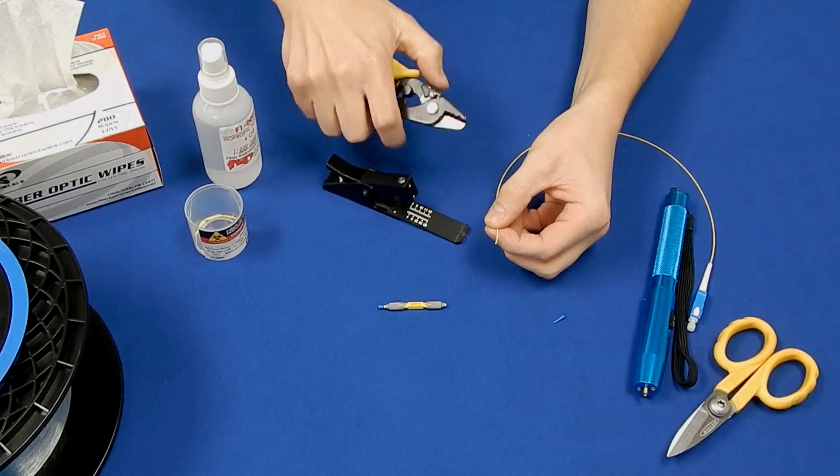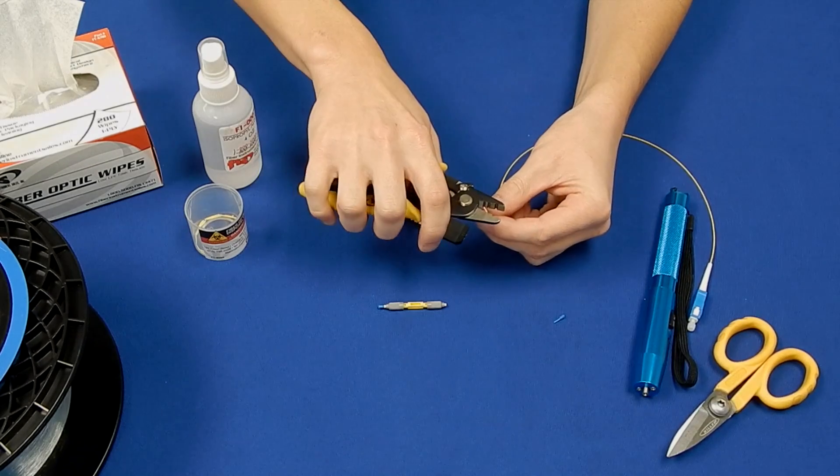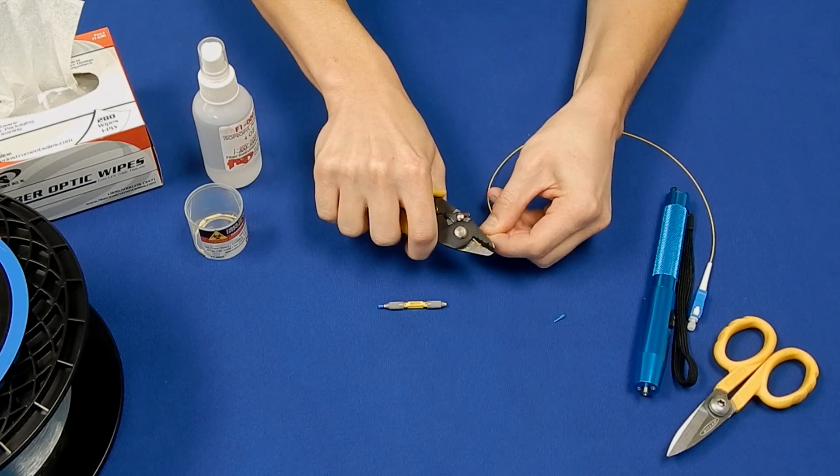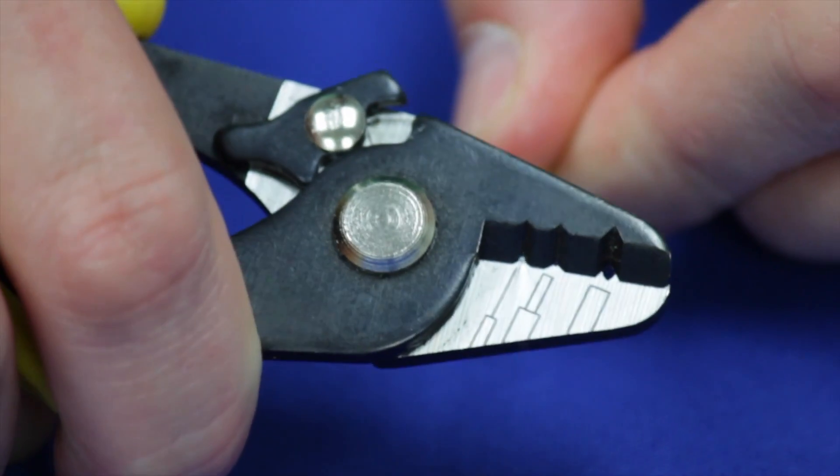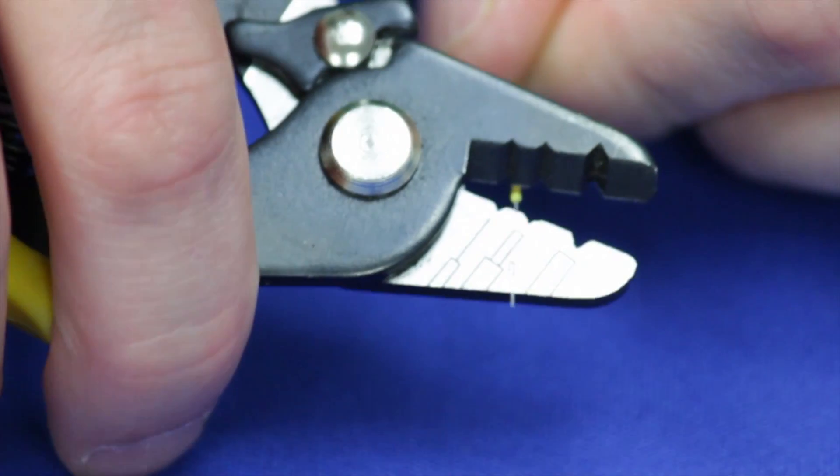Strip an inch to an inch and a half of 900 micron jacket and 250 micron coating from the end of the pigtail. Be sure to remove all of the acrylate coating from the fiber.